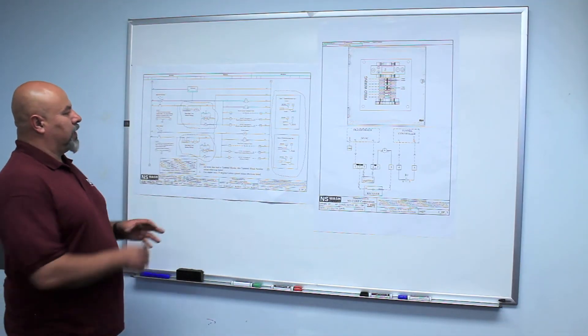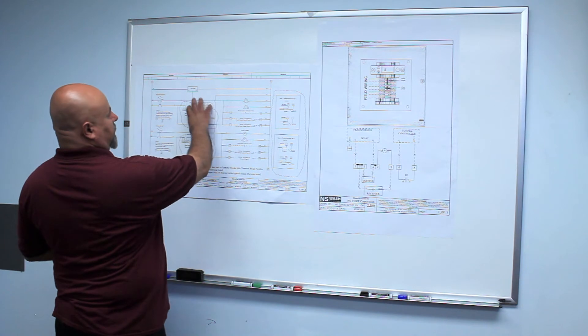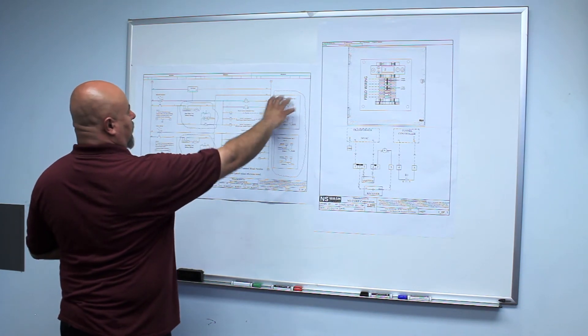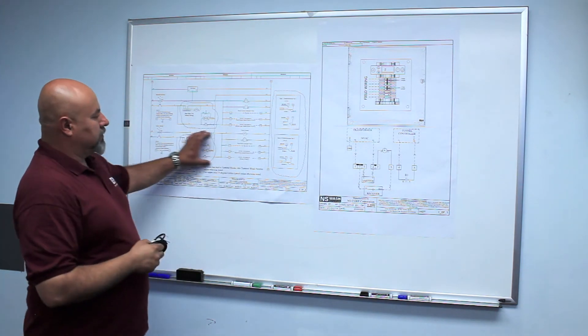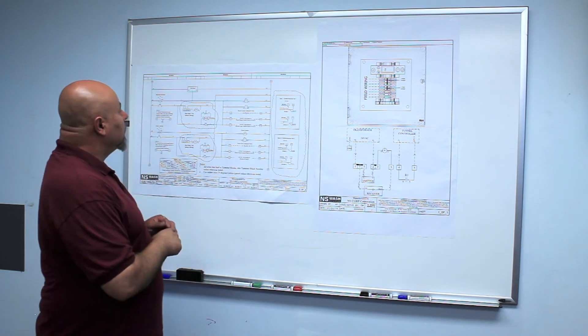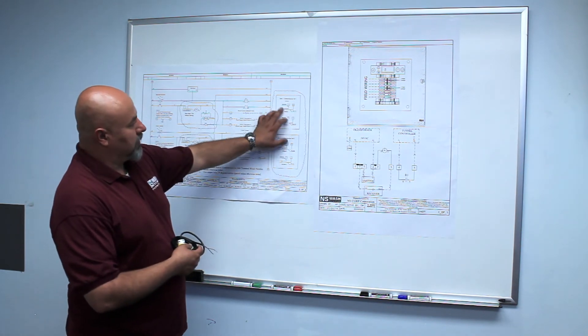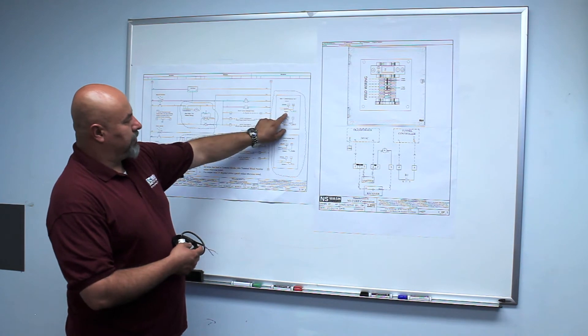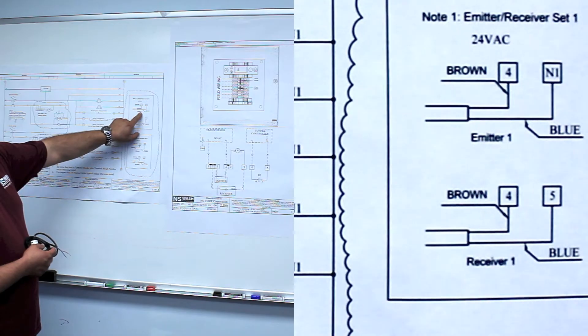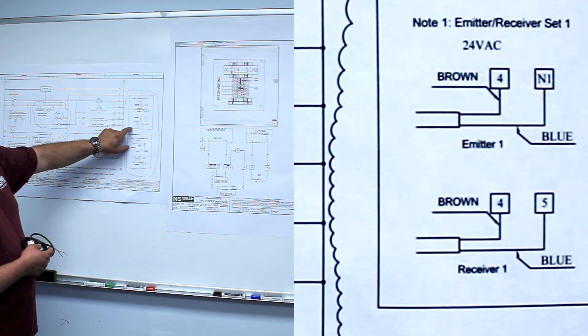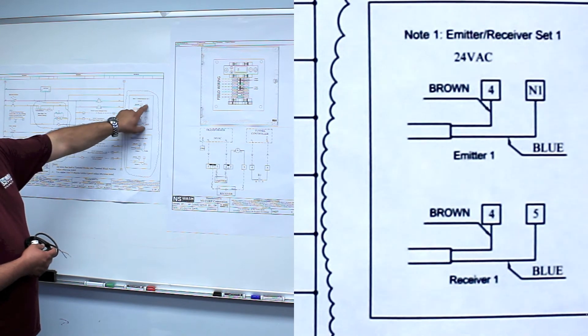We're using two sets of photo eyes here. This set here is one set of photo eyes for activation, and here's another set of photo eyes for activation. And again, you want to identify, it's clearly marked here, the emitter photo eye, brown wire goes to terminal four, the blue wire goes to neutral.